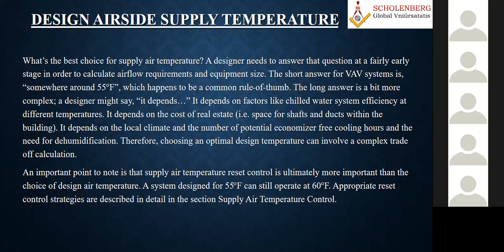Generally, we always have questions on what should be the best choice of supply temperature, because I have defined the comfort condition. ASHRAE has conducted a lot of research on comfort, called the comfort zone in the psychrometric chart, and they define it within a temperature of basically 20 to 25. That is the reason we generally take the inside condition as 23 plus or minus 2 or 3 degrees, so the maximum limit can go up and the minimum limit can go down. To achieve that, what should our supply temperature be? Particularly for a VAV system, I will tell you about the constant volume system also, which is different, and I will explain that at that time. As I told you, supply temperature is ultimately more important than the choice of the design air temperature.